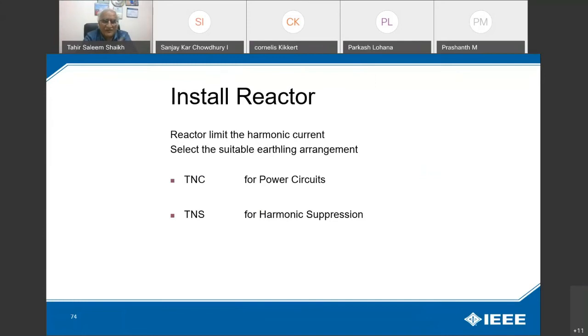For the power circuit, TNC is normally recommended, and TNS is recommended for harmonic suppression. For critical load, IT, where the neutral is not earthed, a single fault will not trip your circuit breaker, and when a second fault occurs, a double fault, the IT breaker will trip. So there are certain limitations.